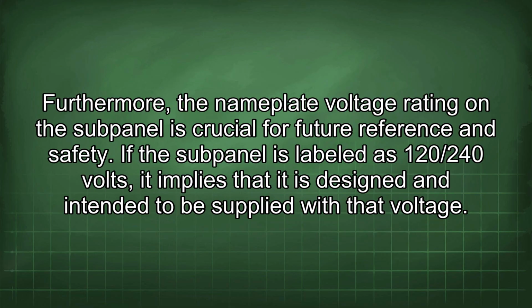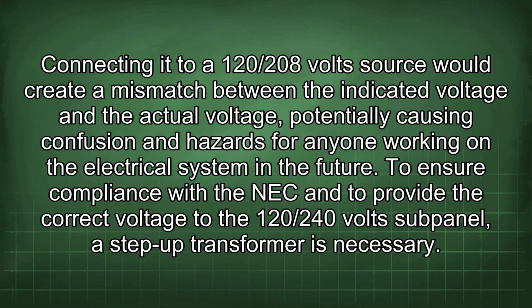Furthermore, the nameplate voltage rating on the subpanel is crucial for future reference and safety. If the subpanel is labeled as 120/240 volts, it implies that it is designed and intended to be supplied with that voltage. Connecting it to a 120/208 volt source would create a mismatch between the indicated voltage and the actual voltage, potentially causing confusion and hazards for anyone working on the electrical system in the future.